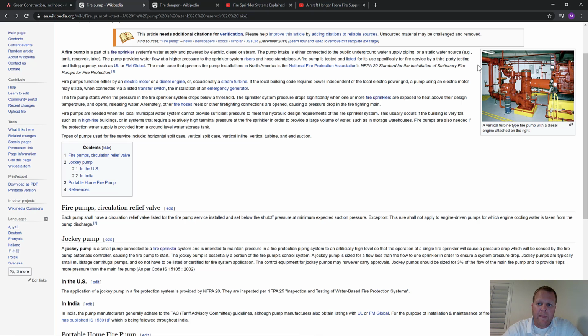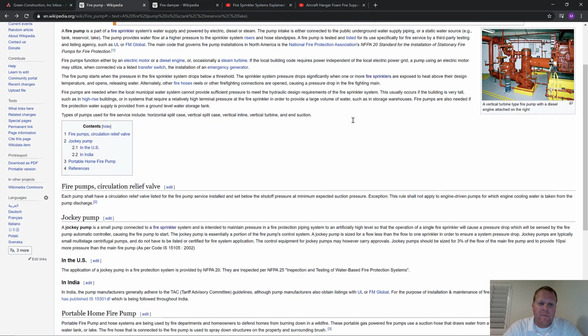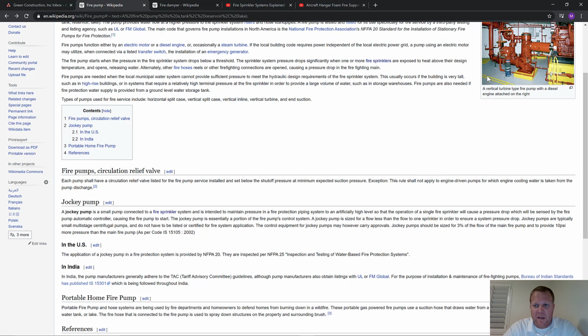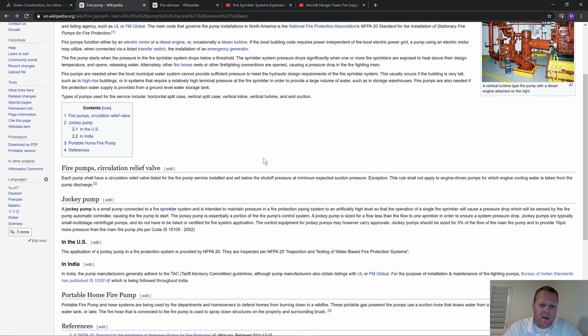But then the fire pump would actually start up, because it monitored that pressure drop. But pressure drop is kind of a funky thing sometimes. Maybe the sprinkler pipe is old, maybe it's leaking, or the backflow preventer is just not perfect, and it's dropping some pressure. So to make sure that this pump doesn't start needlessly, they have this thing called a jockey pump that keeps the pressure in the pipe up, but it wouldn't be enough to provide a lot of water in the event of an actual fire and a sprinkler going off.